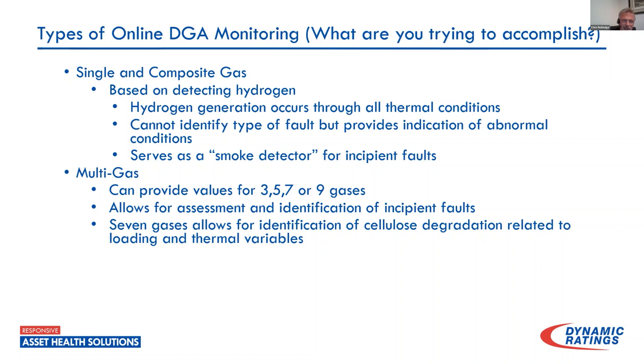I work for Memphis Light Gas and Water — I was there for about 28 years. We went back and forth quite a bit from multi-gas to single gas. When I moved into an asset management role, I looked at what we were using, and with multi-gas it became clear we weren't really using the monitoring to do analytics. Like a lot of companies, if we got an alarm we'd go take a manual sample and investigate further, in which case single gas would really be the way to go. Multi-gas is 40,000 plus dollars; single gas can be as low as a couple grand. So rather than being selective about where to put monitoring, with single gas I could cover a large portion of my fleet while staying within budget constraints.